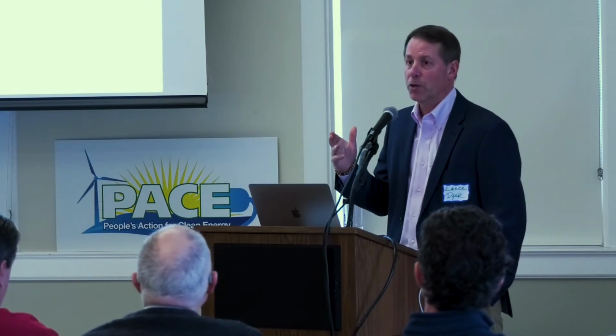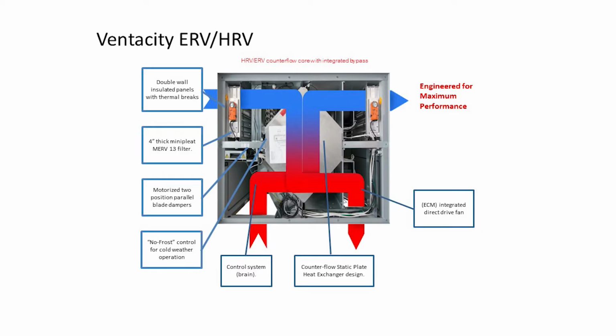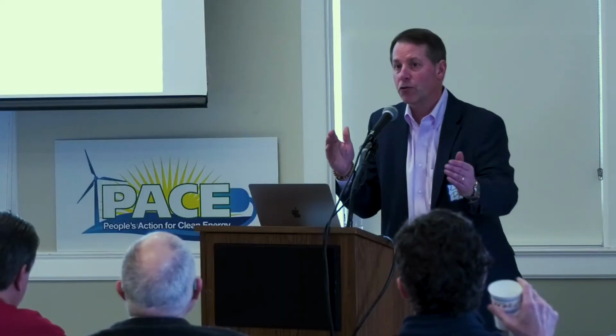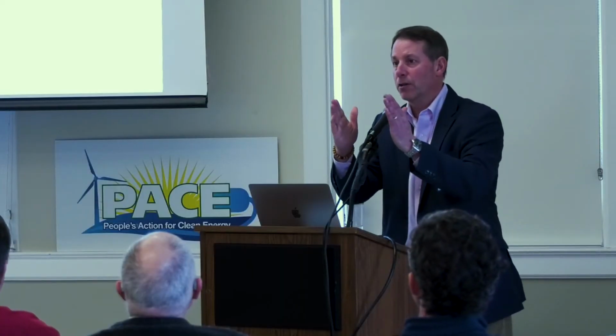It doesn't transfer moisture. But as you can see, the way these work is on the top left, you see the blue ribbon, if you will, coming in. It takes a right turn, comes down through the energy core. It will then get down to the bottom there, take a right, and come into the building. On the left is where we would exhaust stale air, if you will, up and through that core. Now, those streams do not touch each other.